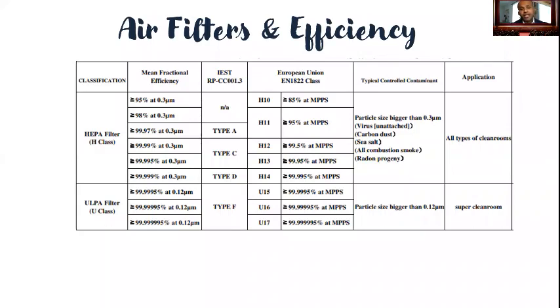HEPA filters are another option for enhanced filtration. HEPA filters can outperform the MERV 16 filter rating. While a MERV 16 filter captures more than 95% of particles in the entire size range tested, a HEPA filter captures 99.97%. HEPA filters are so efficient, they can cause a higher pressure drop than even MERV 16 filters. And then there are ULPA filters, which stands for ultra low penetration air, which are mostly used in super clean rooms.